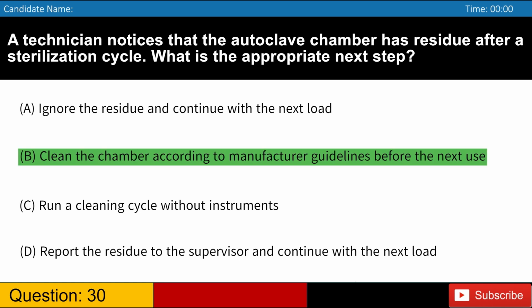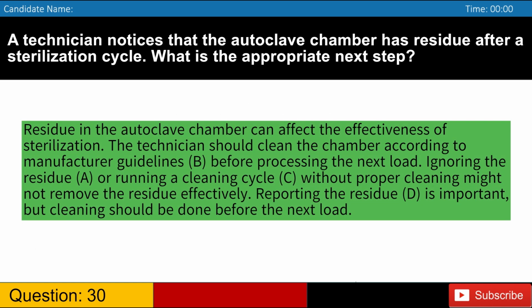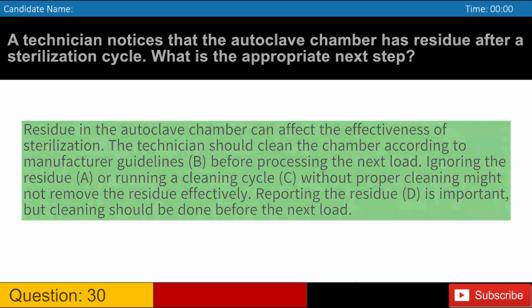Answer: B. Residue in the autoclave chamber can affect the effectiveness of sterilization. The technician should clean the chamber according to manufacturer guidelines, B, before processing the next load. Ignoring the residue, A, or running a cleaning cycle, C, without proper cleaning might not remove the residue effectively. Reporting the residue, D, is important, but cleaning should be done before the next load.